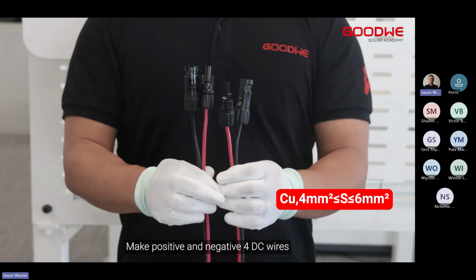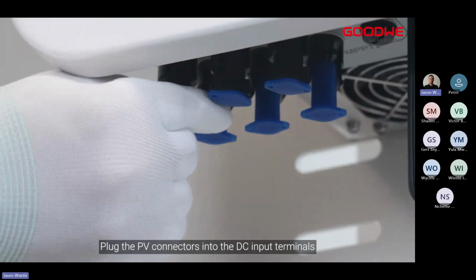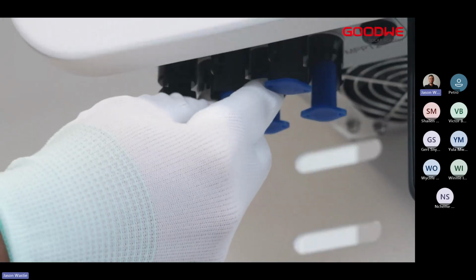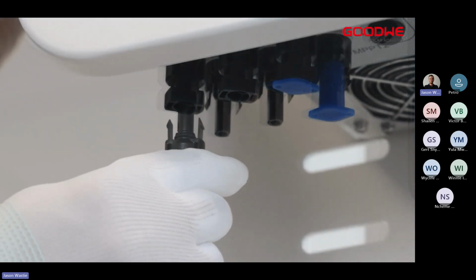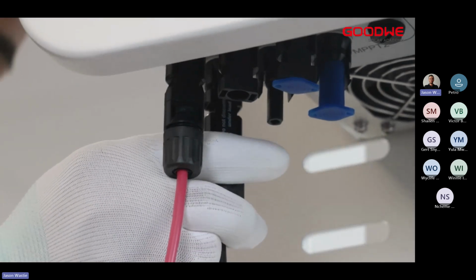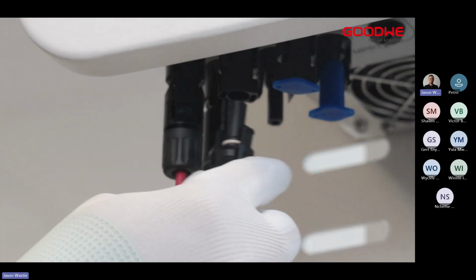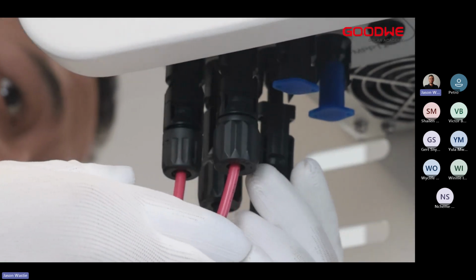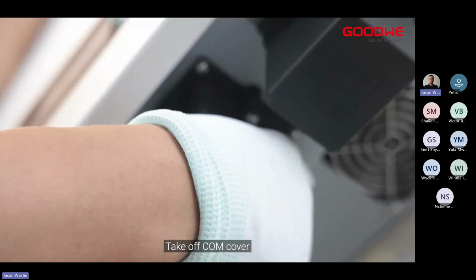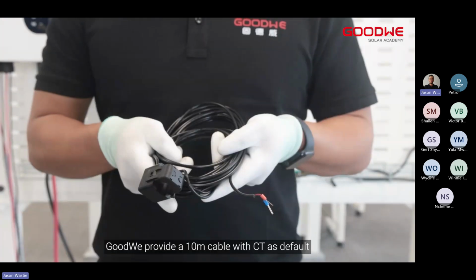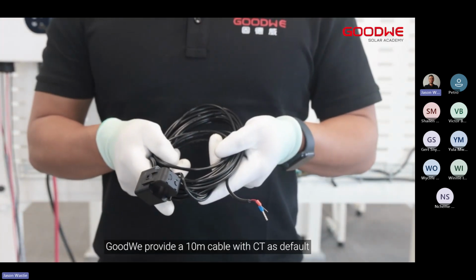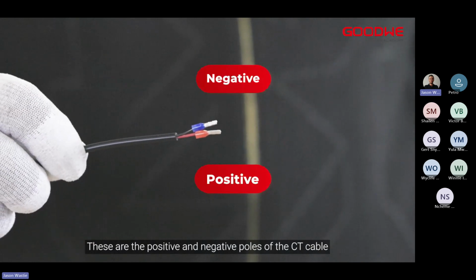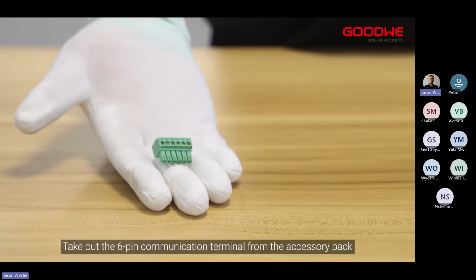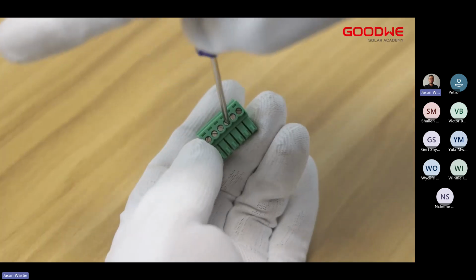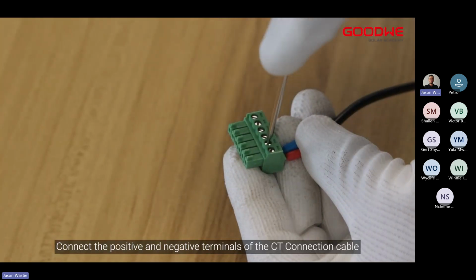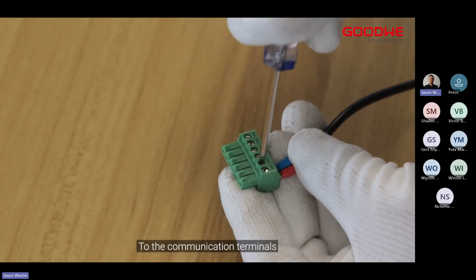Make positive and negative 4 DC wires. Plug the PV connectors into the DC input terminals. Take off COM cover. GoodWe provide a 10M cable with CT as default. These are the positive and negative poles of the CT cable. Take out the 6-pin communication terminal from the accessory pack. Connect the positive and negative terminals of the CT connection cable to the communication terminals.